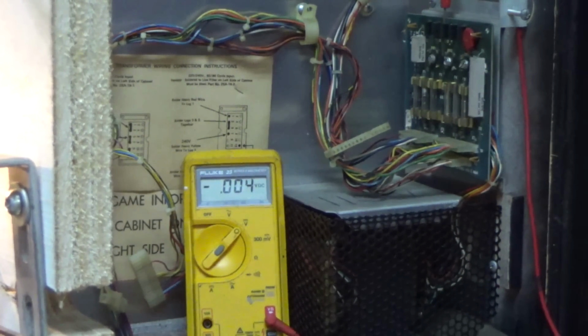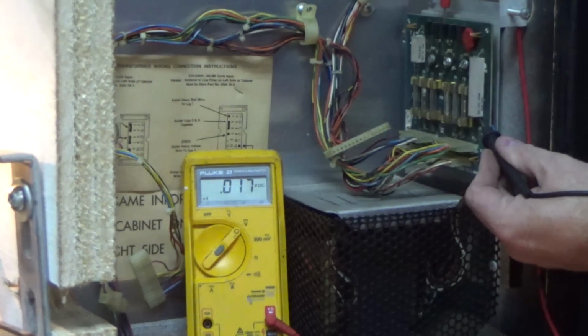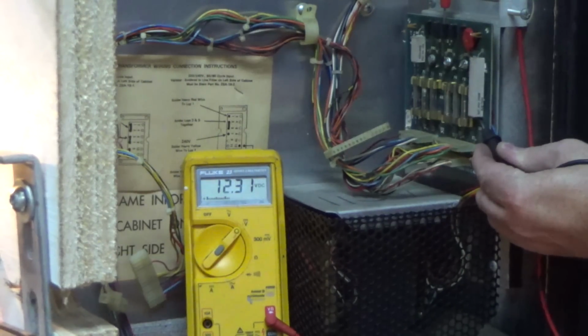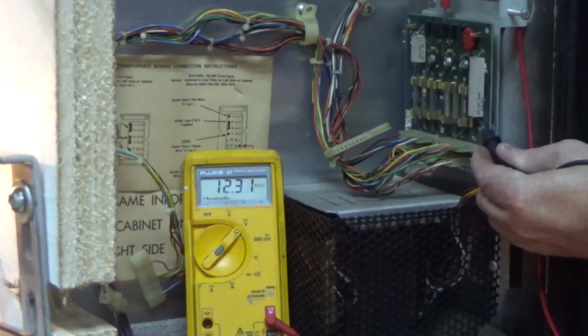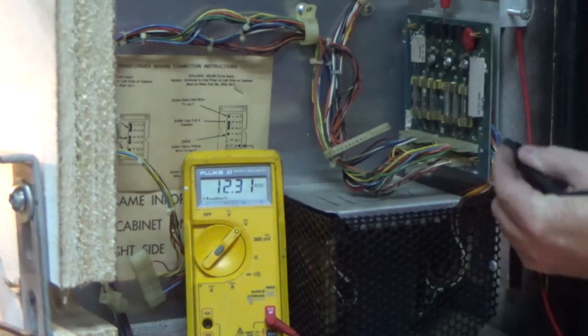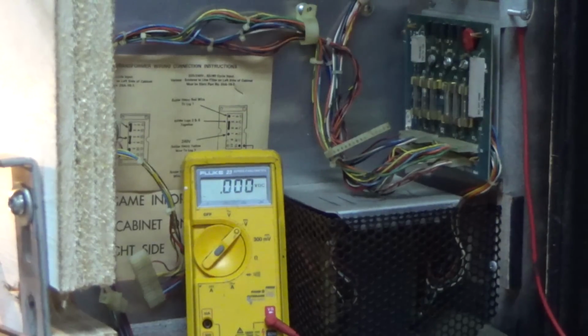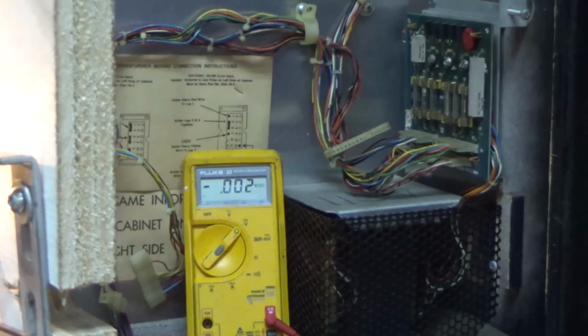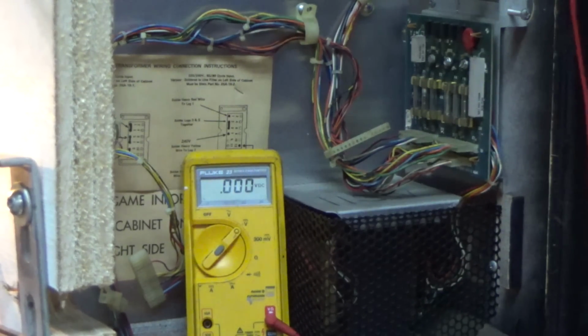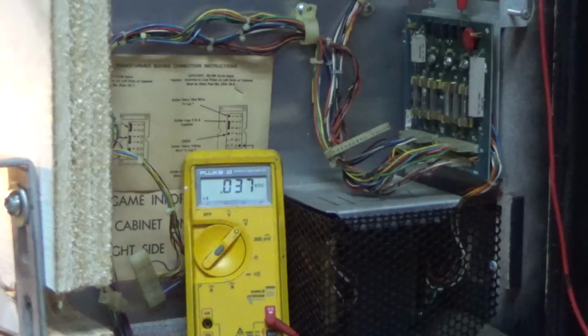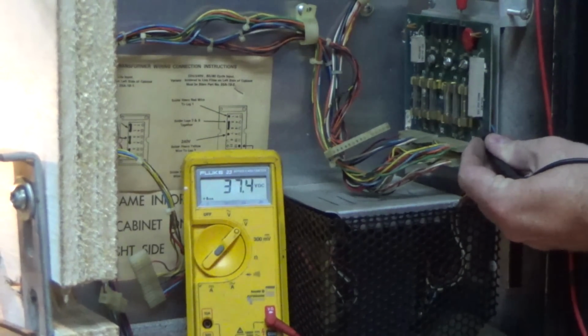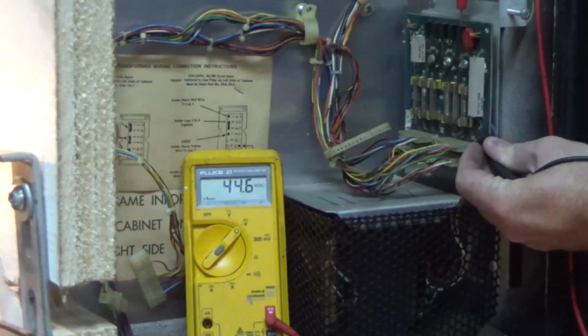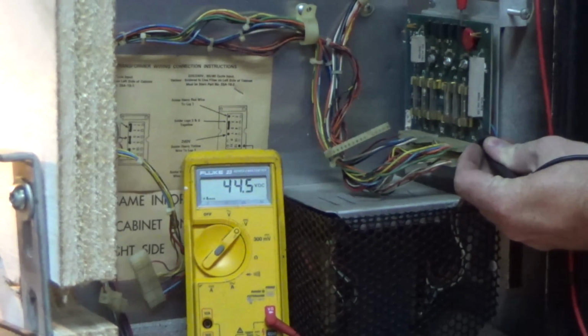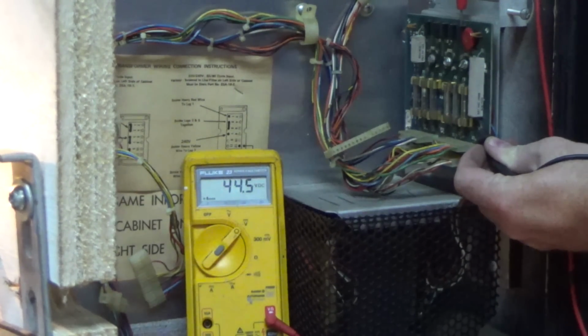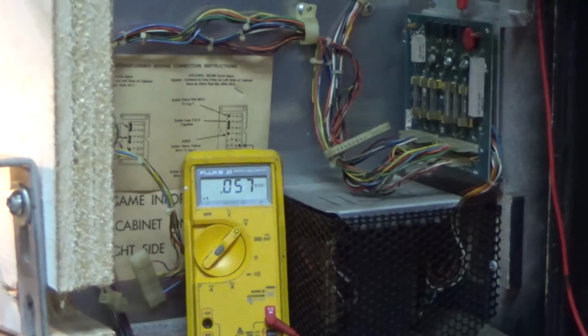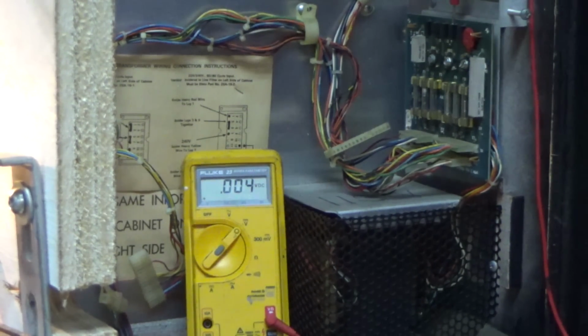Test point 3, here we go: 12.3, it's supposed to be 11.9. Notice it is also 0.4 high, like our other one was. Test point 5, we're going to skip 4, I'll tell you why in a second. Test point 5: 44.6 volts, it's supposed to be 43 volts. That is the solenoid voltage. So that's actually slightly high, but again, it's because the input voltage is slightly high.